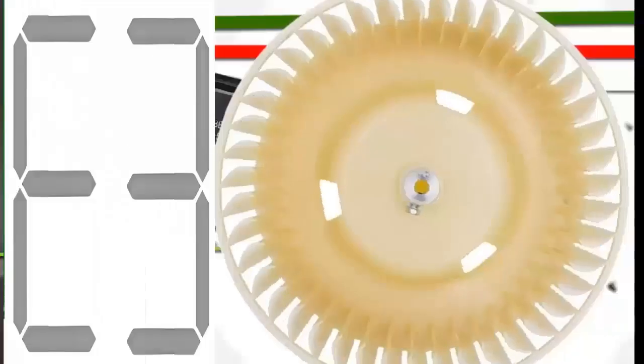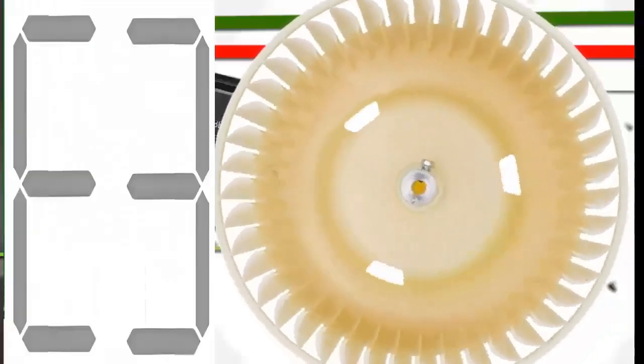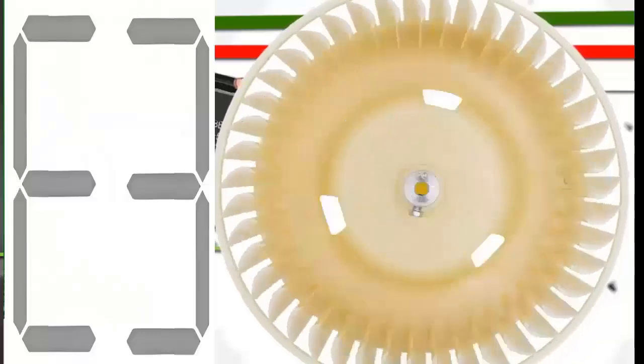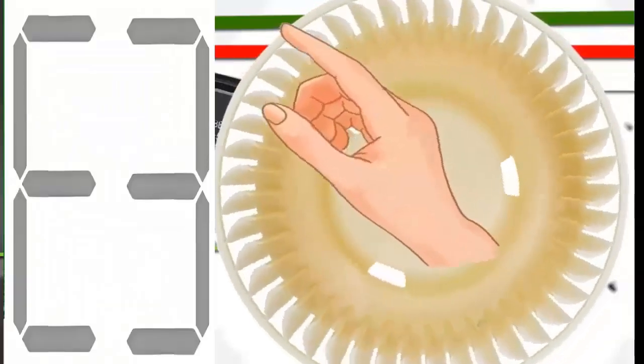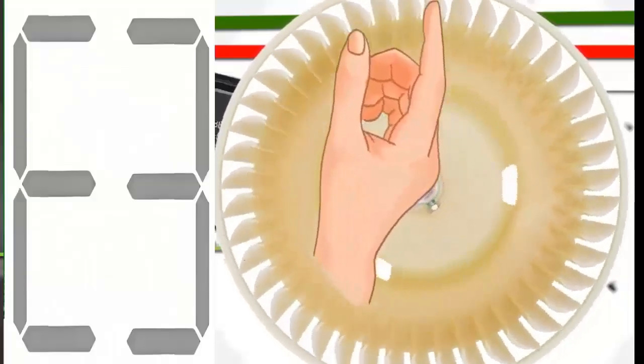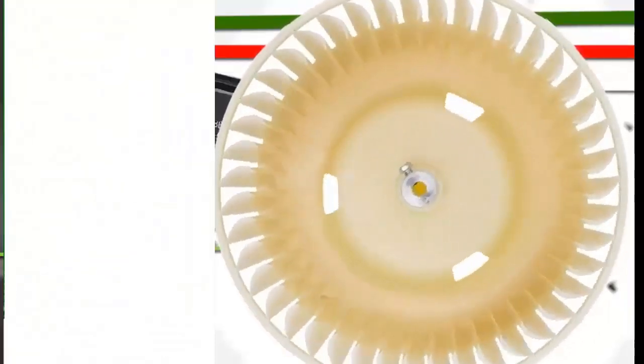1. If the fan exhibits issues, such as not spinning or spinning slowly, the first thing to do is to manually spin the fan blade, with the unit turned off. Check that the rotation is smooth, with no obstructions or unusual noises, to rule out issues with jamming or bearings.